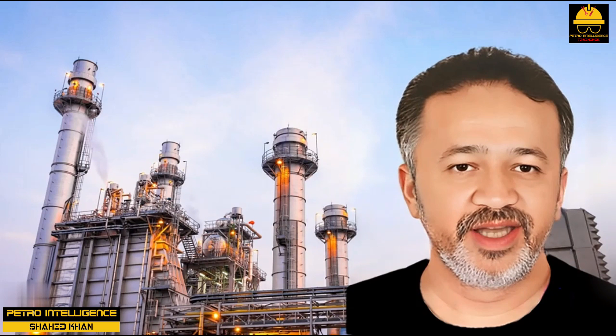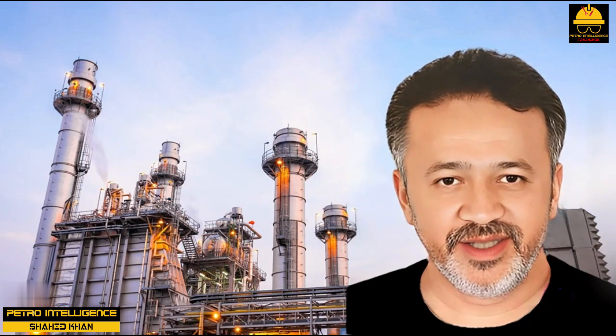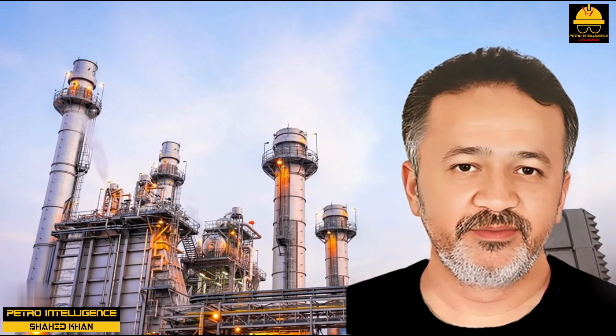It is rather like a large flywheel. Even after we stop cranking the wheel, the rotational energy stored by the wheel keeps it spinning. Even when all the firing is stopped, the energy stored in the refractory walls continues to radiate heat to the process tubes. But without flow, there is no way to carry the heat away from the tubes. Therefore, the tubes overheat.